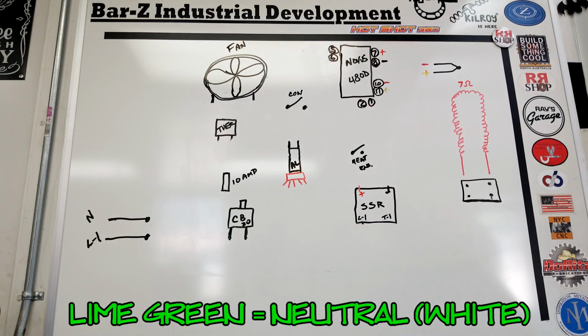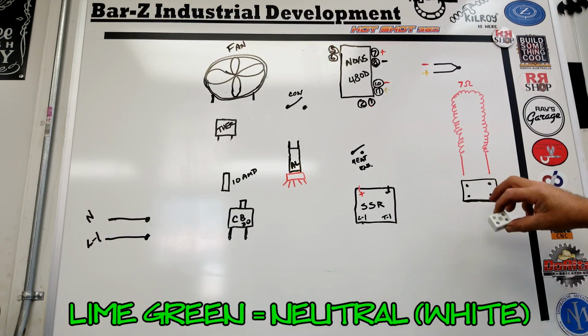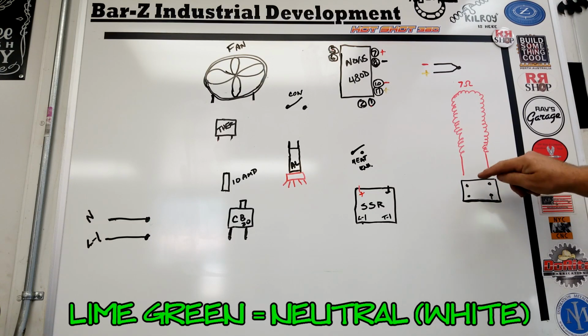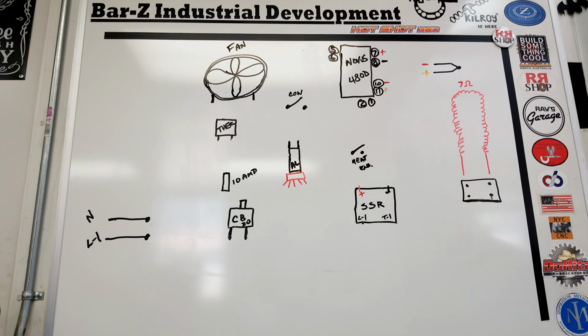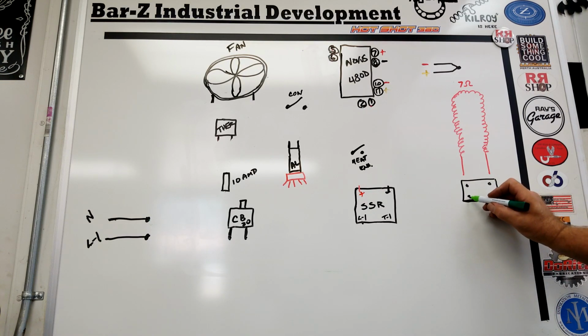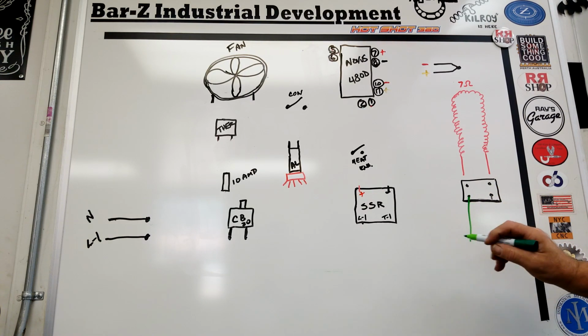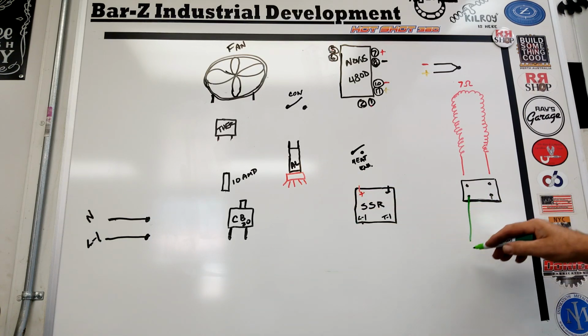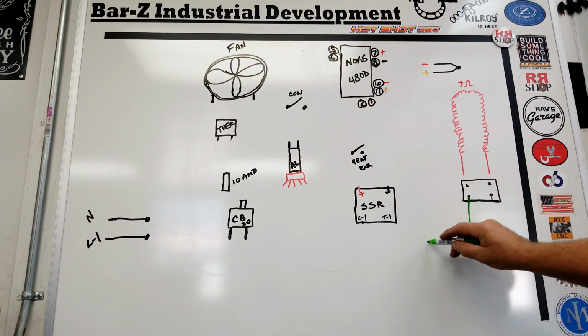The first thing I'm going to hit is the terminal block, which is this. This is representing, and that goes off to your element. So we're going to hit this with neutral first and foremost, and we're going to bring, basically within the unit, the power cord neutral straight to that terminal block.